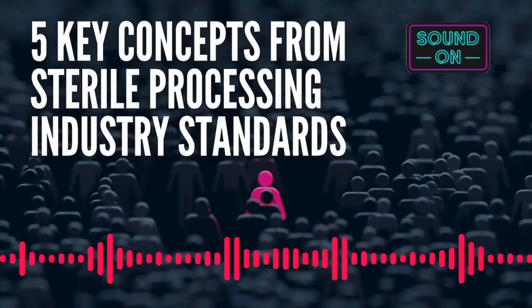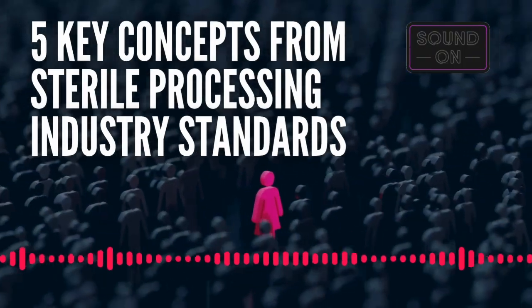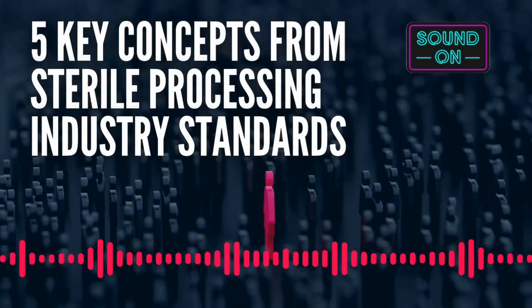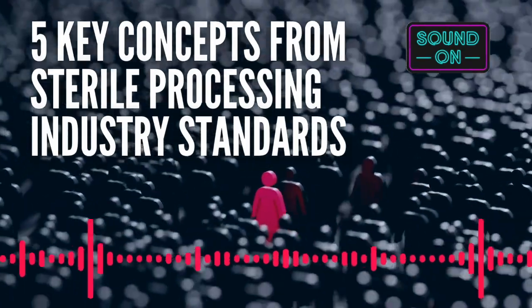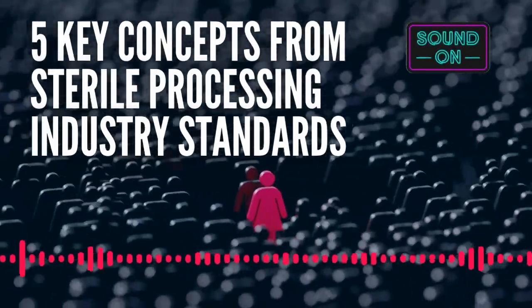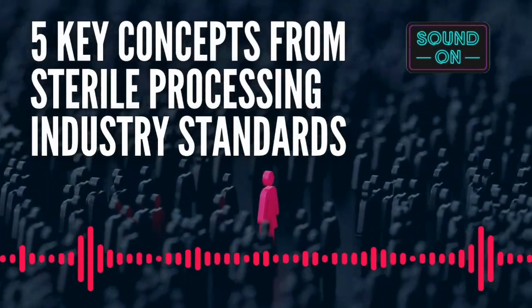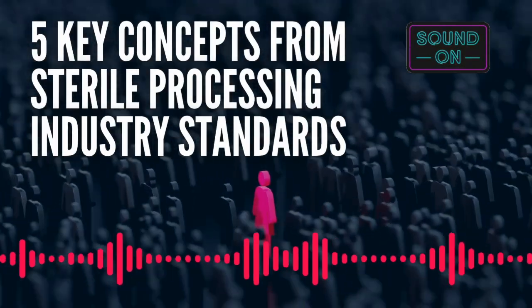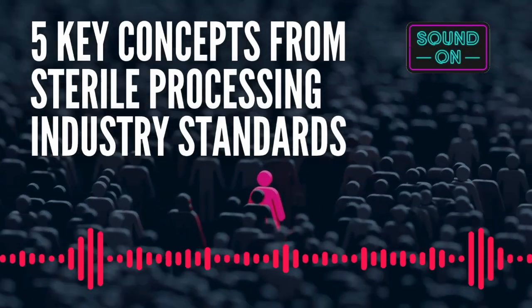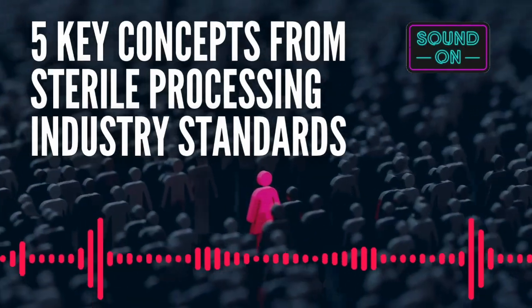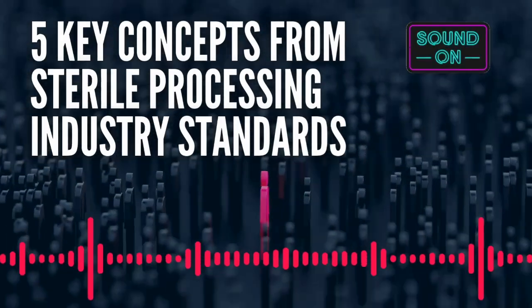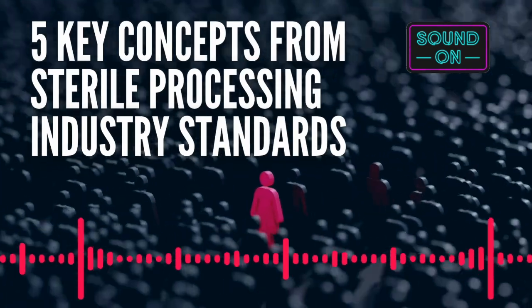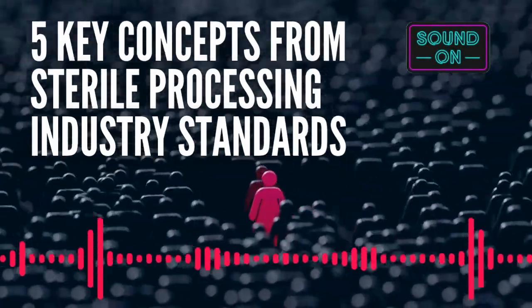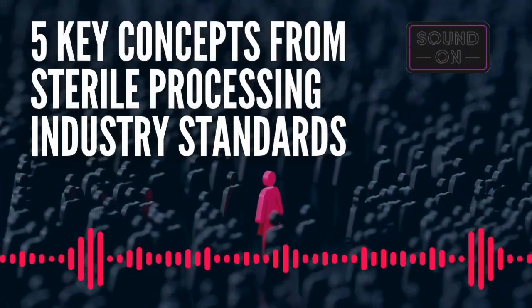Of course. So you have gravity displacement, where steam goes into the chamber and forces the air out. And then you have dynamic air removal, where a vacuum pump actively sucks the air out before the steam even gets in there. So it's like choosing between a regular oven and a convection oven. Exactly. They both cook the food, but one uses forced air circulation to heat things more evenly. Got it. So it's all about how the air is removed before the steam does its job.